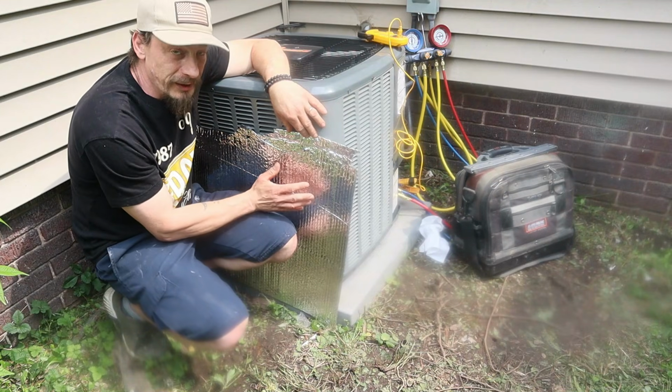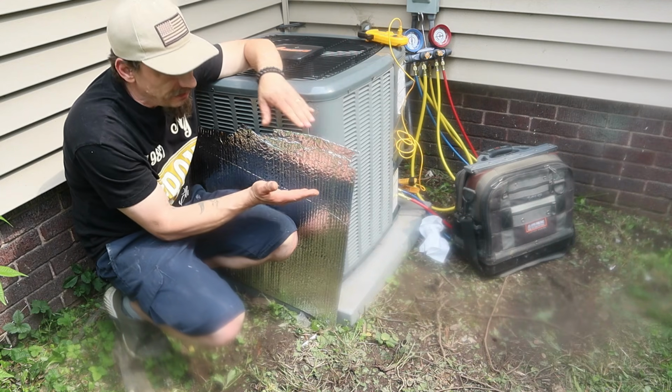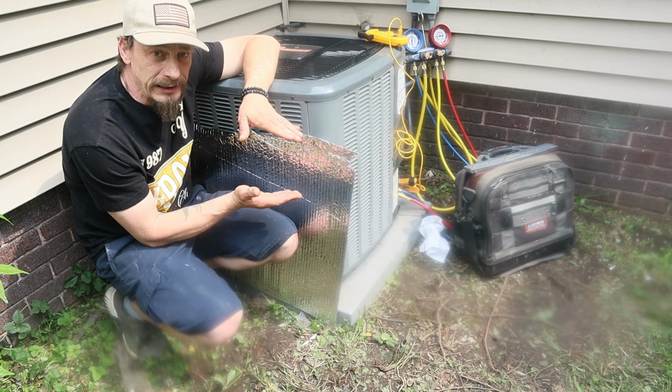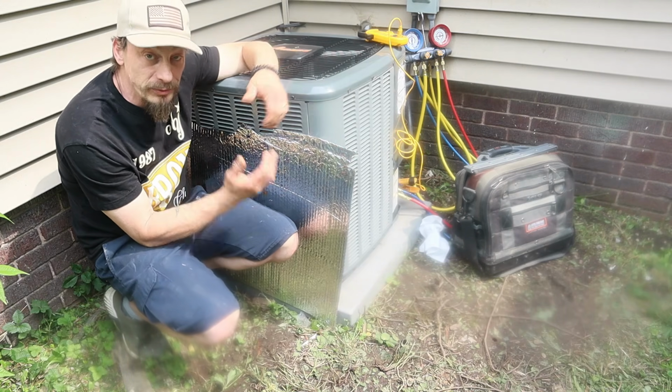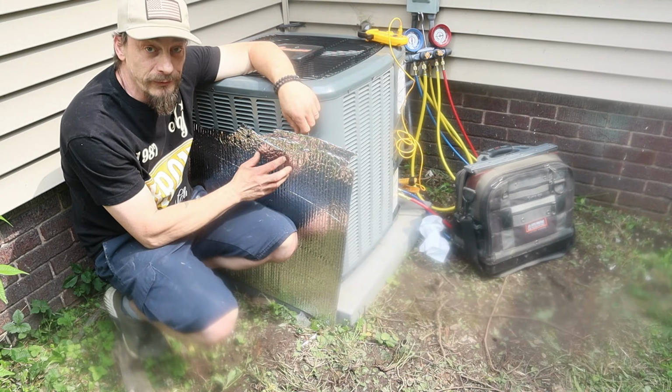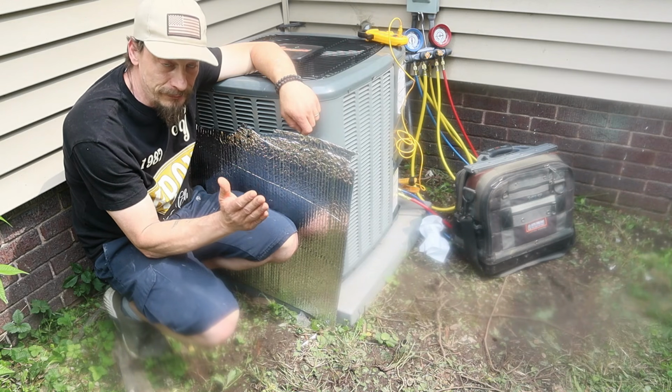When we blocked off the airflow going through the sides, what happened was that we took away that tight little zone where the refrigerant was flashing over into a liquid very quickly, and we completely spread it out because that refrigerant was no longer rapidly cooling off. That's why we saw an increase in our head pressure.